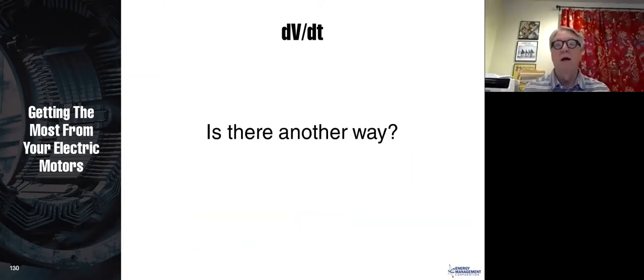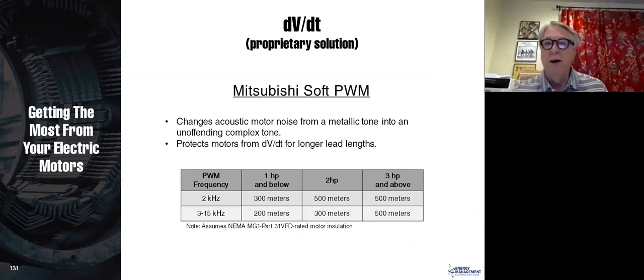Now, is there another way? I'm mentioning a supplier here, probably our favored supplier, Mitsubishi. They have something called soft PWM. And the rule of thumb is that anytime you have a motor, even if it's a high spike wire, VFD rated motor, if the cable is more than 100 feet between the motor and the drive, you should apply a dV/dt filter. And what that will do, of course, is reduce those spikes, and it will reduce those spikes to below 1000 volts.